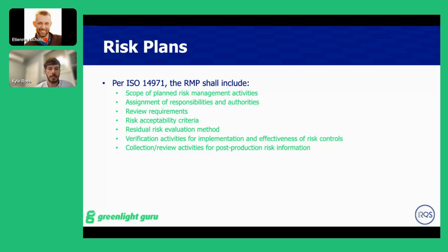Also, this should be tied back to your high-level procedure for risk as well. The residual risk evaluation method, verification activities, and effectiveness of risk controls. So once you have controls in place, you need to go back and verify they're actually working. And then how you're going to collect and review activities for post-production risk. Another thing that's not clearly defined here is when you should review risk. Similar to design reviews, you should also have planned risk reviews. That can be at different phases of your risk review, or once certain things are done, having those formally reviewed as well.